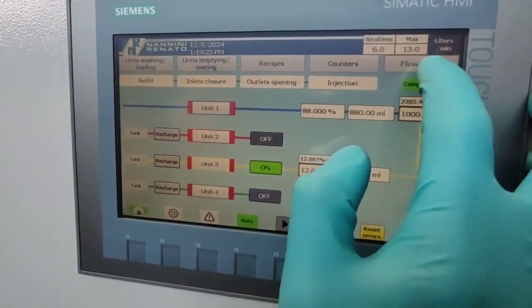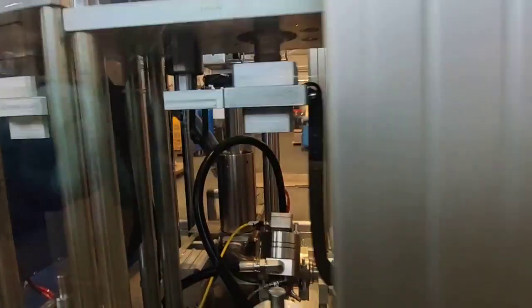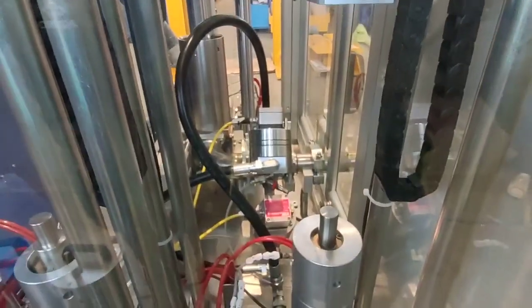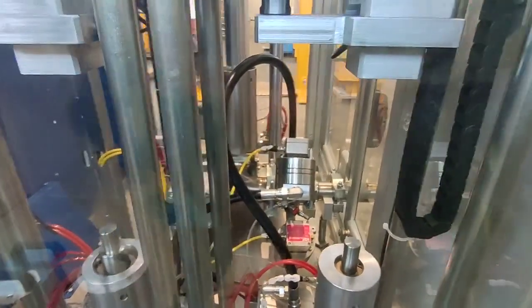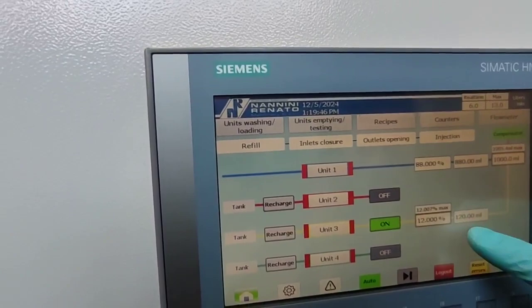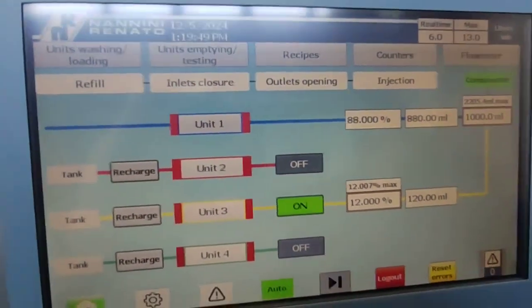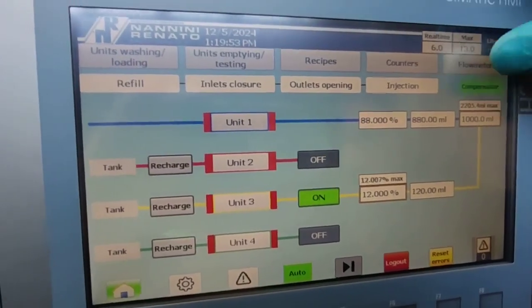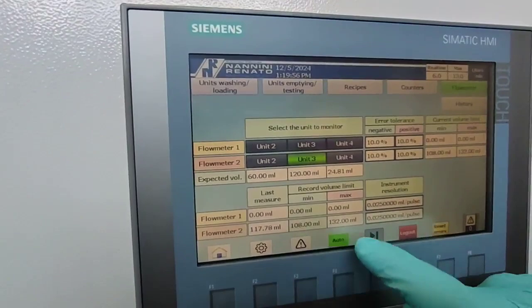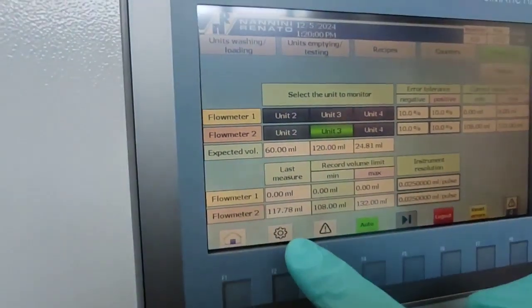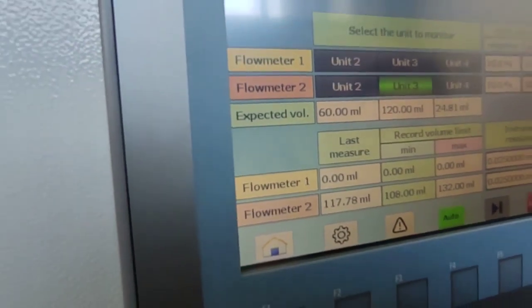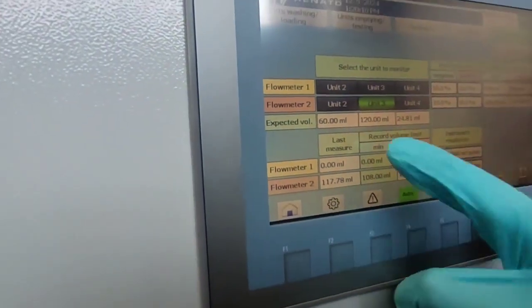I can show you here that you have two flow meters checking out if the additive product flowing out from the dosing unit is actually the same as you have set on the HMI display. And now we are going to dose out 120 ml. So the flow meter checks if actually the product coming out is 120. We have a little tolerance of 10% here and it has just measured 117.78 ml coming out, which is very close to 120 ml set by the system.